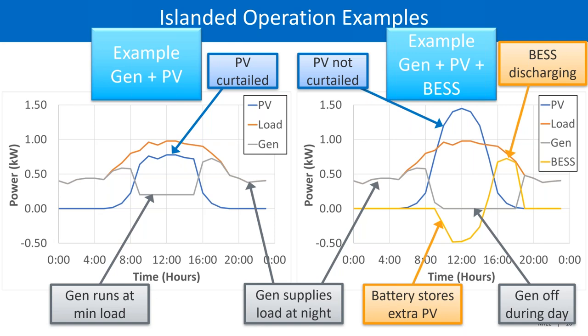But when the PV production starts going up and goes past what your load is, at that point you can actually turn the generator off. The energy storage unit can provide the voltage for the PV array to push against. So not only is the PV providing all of the power for the load, but it's also charging your battery.